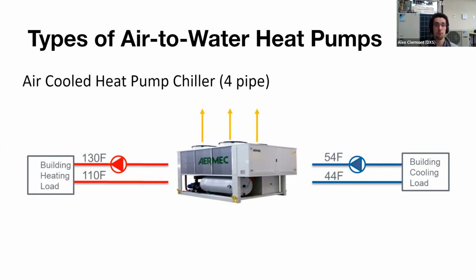In terms of advantages, this is a bit of a newer technology, but there are some advantages to going with these kinds of machines. If you have an existing hydronic infrastructure in your building, these can make a ton of sense. Instead of running your refrigerant lines everywhere, the existing hydronic infrastructure can actually be reused in some cases. These still have refrigerant inside of them, but there's actually no refrigerant throughout the building. So that's another little bit of an advantage, and there's less of a chance of a leak. They also allow for a quicker transition to lower GWP refrigerant, which we'll talk about in a little bit, but it's quite helpful that it's all dedicated into the outdoor unit for those machines.